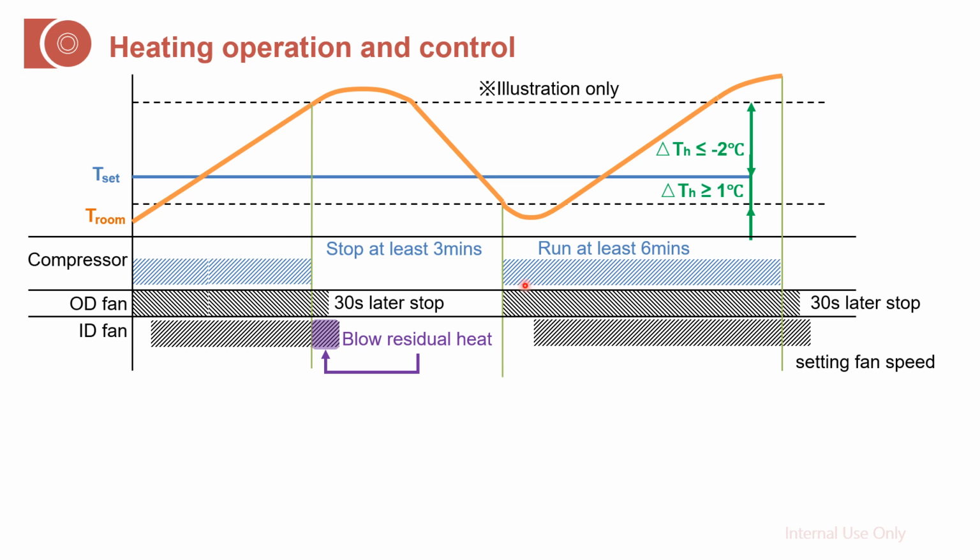And here I'd like to emphasize that once we turn on the compressor, it will operate for at least 6 minutes, which means during these 6 minutes, even if the temperature reaches a very high value, it will not stop. This is just to avoid the compressor frequently switching on and off, to protect the compressor.